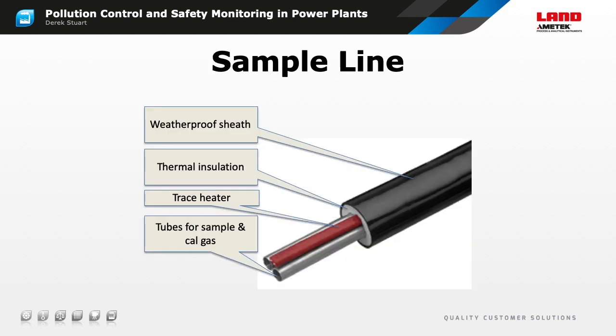Depending on the local environmental conditions, a freeze-protected sample line may be needed between the sample point and the analyzer to prevent moisture from the flue from freezing and causing a blockage. 2 sample tubes are generally used, one for the gas sample and one for the calibration gas returning to the probe. Running the cal gas up to the probe allows us to correct for any losses and also ensures that a leaking or blocked sample system will not go undetected.